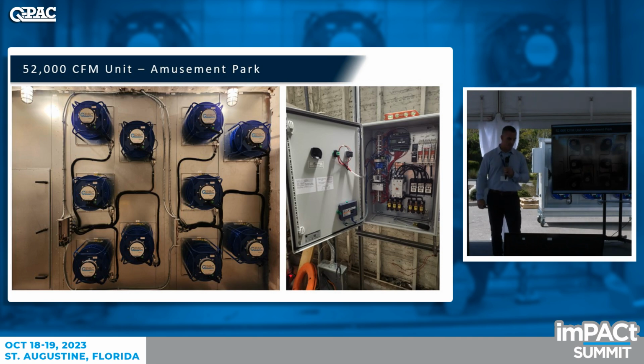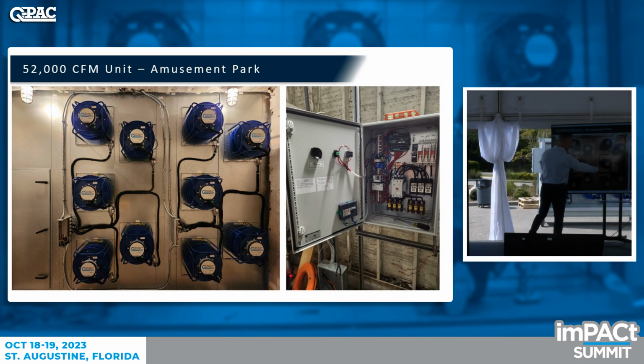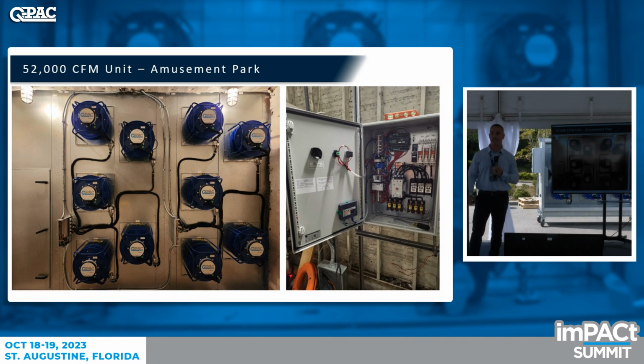And this is our final product, with the 2 quick connects here. So when you're talking with your contractor and you have 2 quick connects, make sure they understand they have to run that extra set of power wire over to the quick connect, and you gotta run 2 sets of control wire. What they did on this job is they ran 2 sets of 8 conductor control wire in the same conduit. So they ran the control wire in and then continued the second set over to the other quick connect. Rather than running extra conduits, they ran the 16 conductor wires in the same conduit.